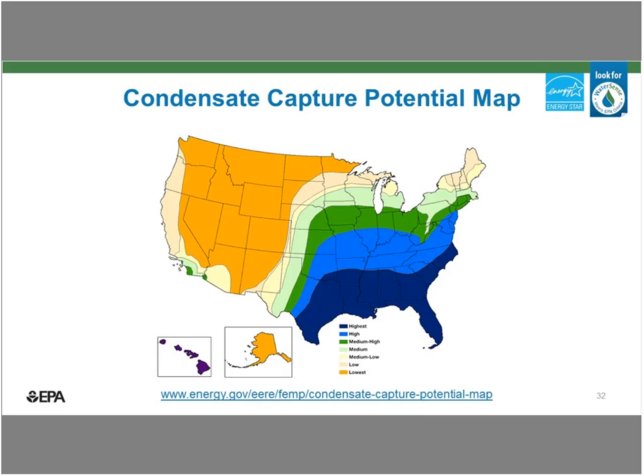The Federal Energy Management Program, or FEMP, has created a really nice resource to help facility managers determine potential for condensate capture. As you can see on this map, facilities in the Southeast, Mid-Atlantic, and Midwest all have really high potential for these types of projects. That being said, cost-effective projects to collect and use condensate for cooling tower makeup can really be feasible in other regions as well, especially where air handlers are close to cooling towers. So certainly look into it regardless of where you're located. FEMP also has similar maps for rainwater and reclaimed wastewater availability, which are two other potential sources of cooling tower makeup water.